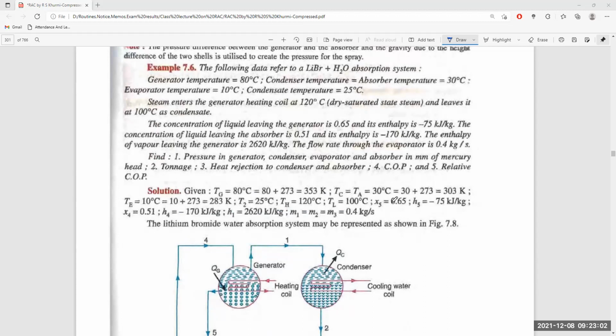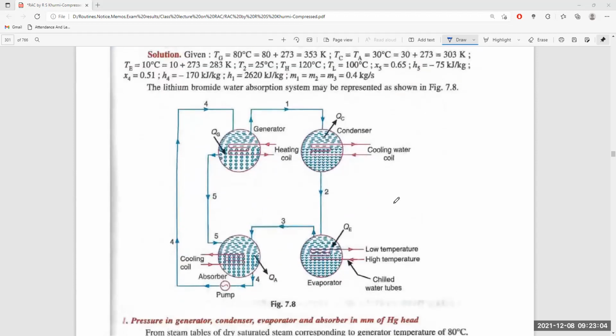And T5, the absorbent coming inside the absorber, X5, that is the concentration of lithium bromide in the weak solution coming back to the absorber, is 0.65. H5, that is the enthalpy content, is minus 75 kilojoule.